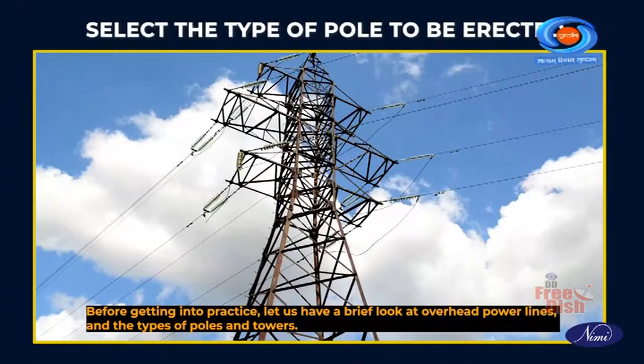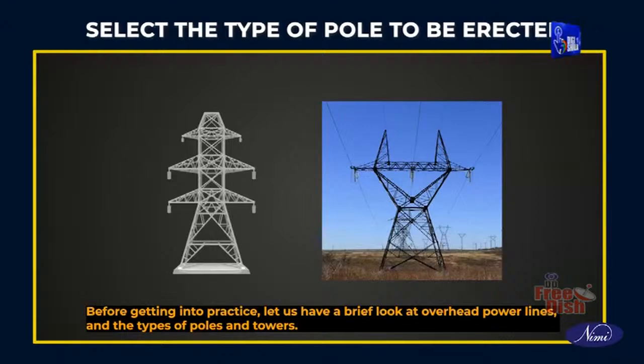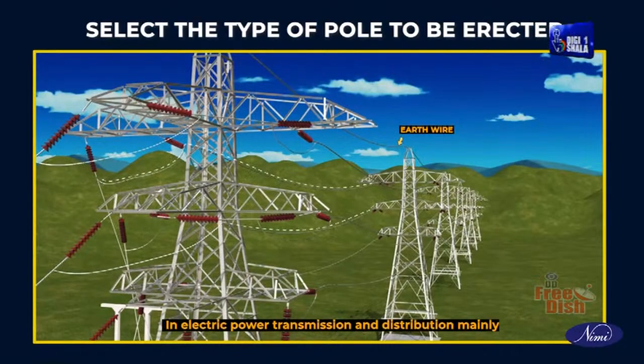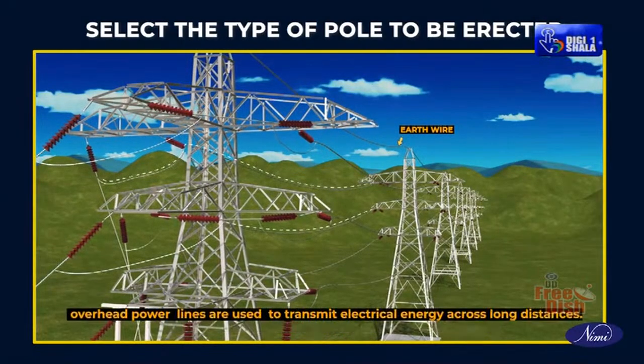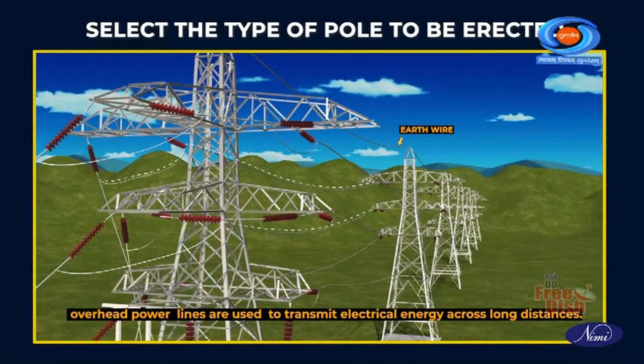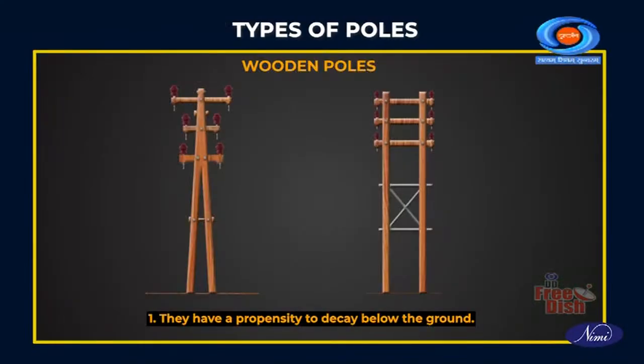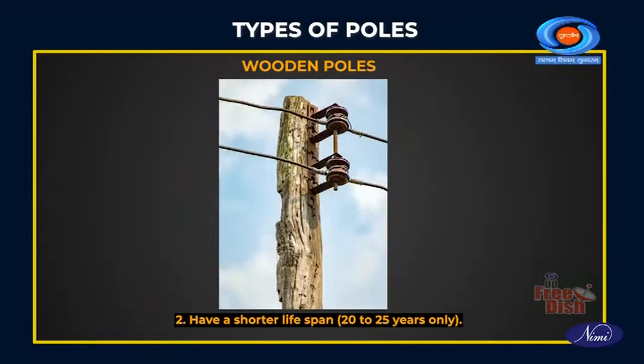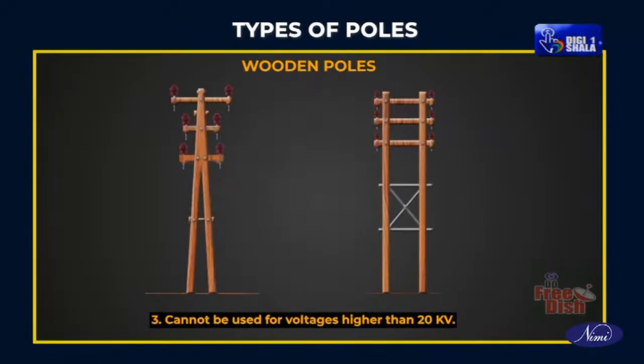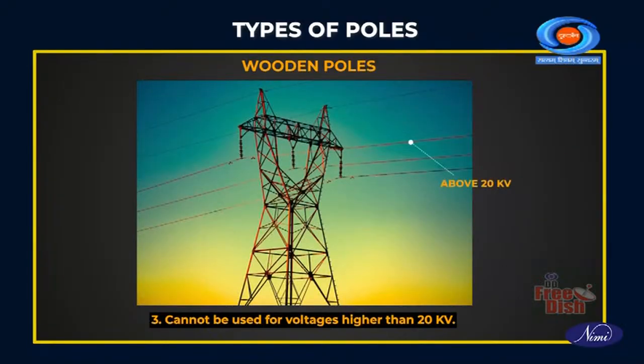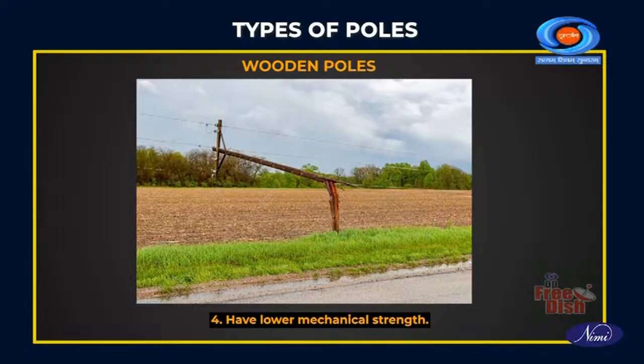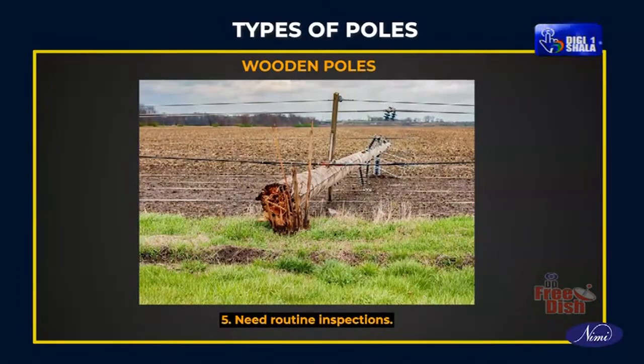Before getting into practice, let us have a brief look at overhead power lines and the type of poles and towers. In electric power transmission and distribution, mainly overhead power lines are used to transmit electrical energy. Wooden poles have a propensity to decay below the ground, have a shorter lifespan, say 20 to 25 years only, cannot be used for voltages higher than 20 kilovolts, have lower mechanical strength, and need routine inspections.